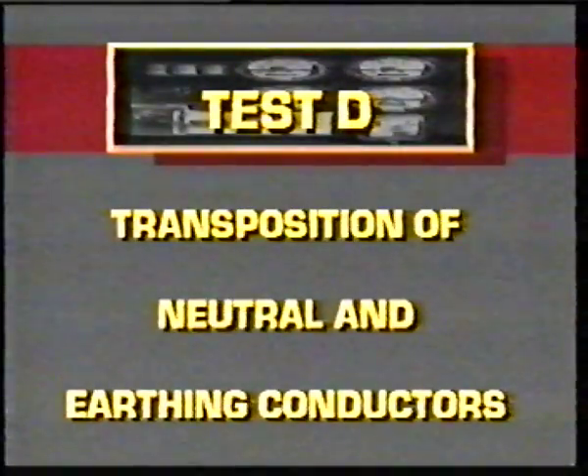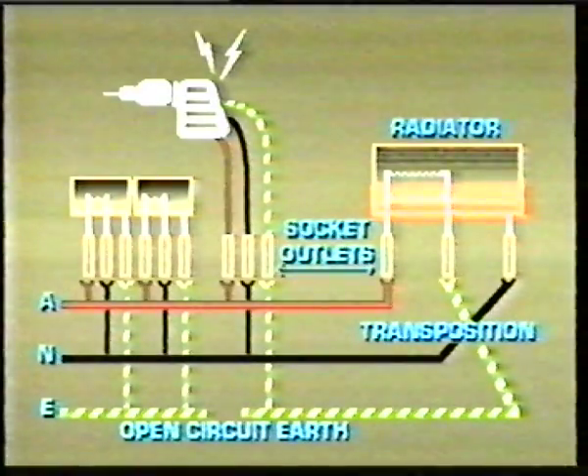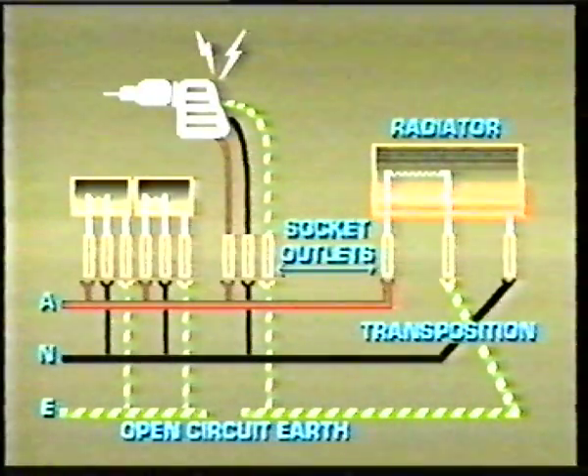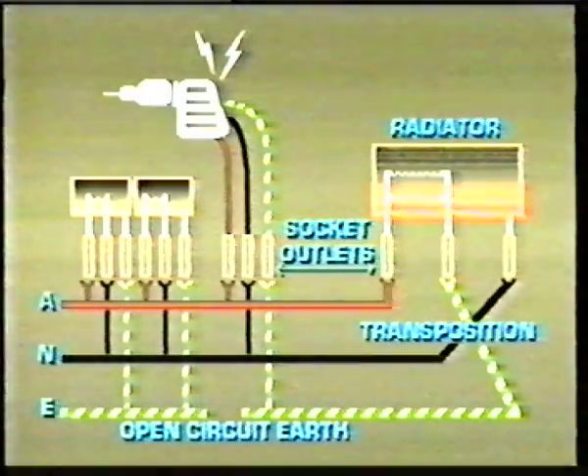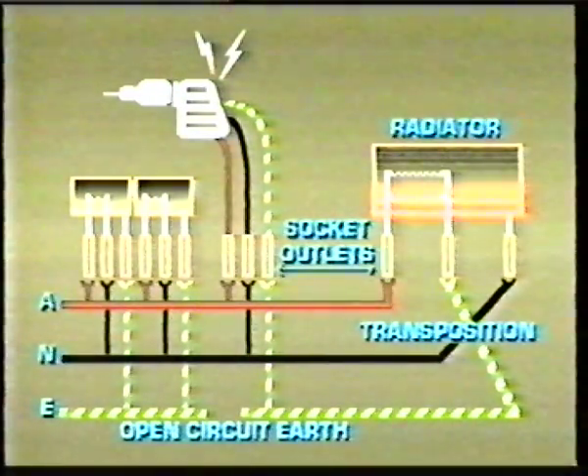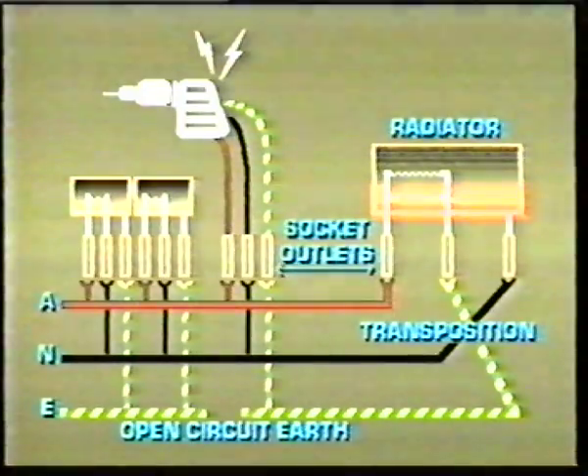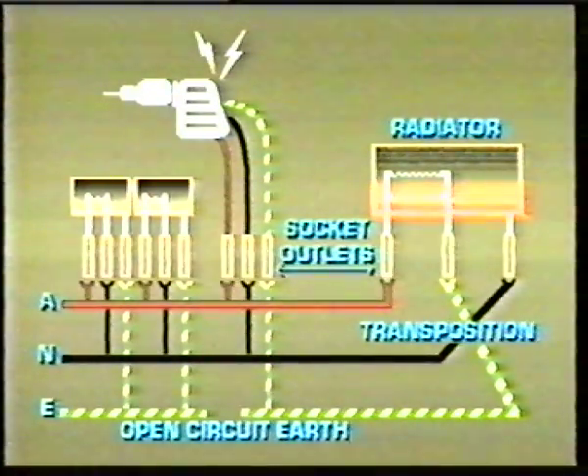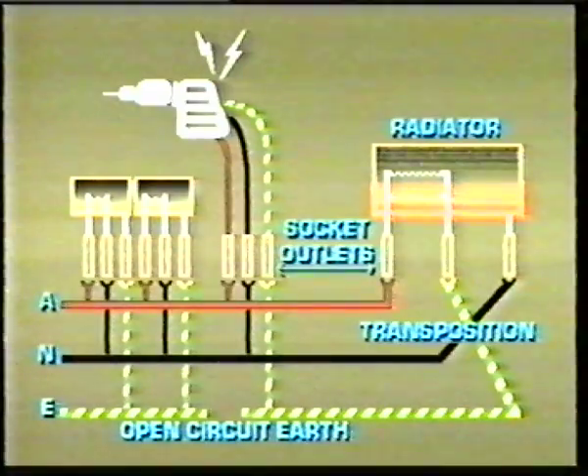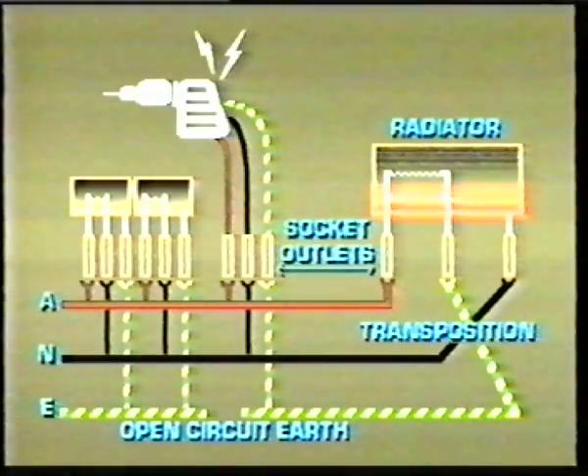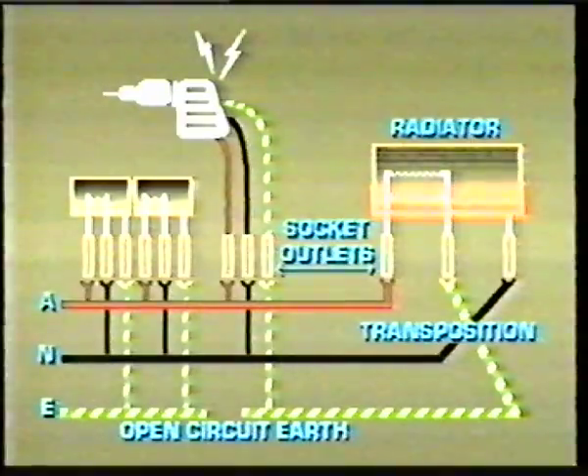Transposition of neutral and earthing conductors arises when the neutral conductor is mistakenly connected to the earth terminal of a piece of equipment and the earthing conductor is connected to the neutral terminal. The earthing conductor then becomes the current carrying conductor and is therefore dangerous. The transposition isn't obvious under certain operating conditions, but is unsafe if the earthing conductor becomes open-circuited, causing one side of the conductor and any exposed metal connected to it to become live. The earthing conductor becomes overheated by carrying the load of the larger neutral conductors, or work is carried out on a live earthing conductor.